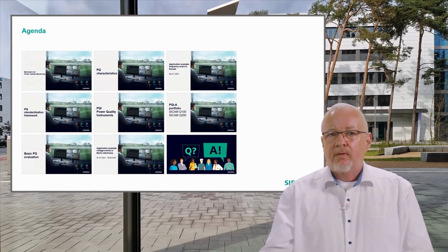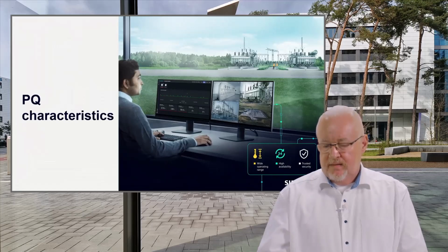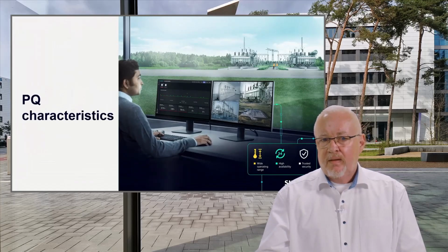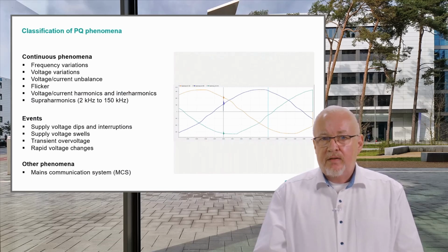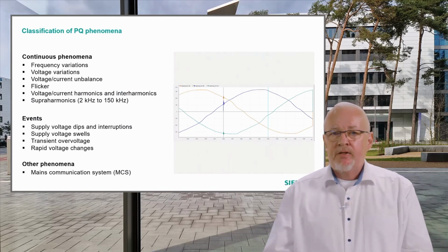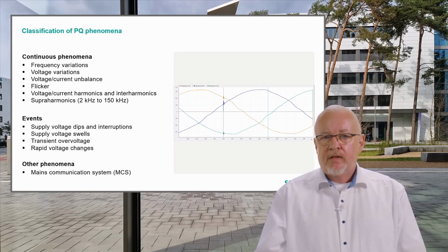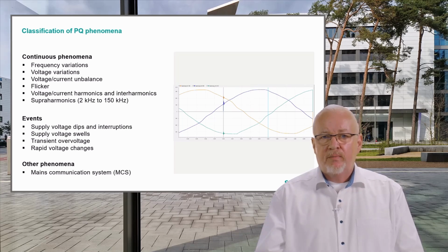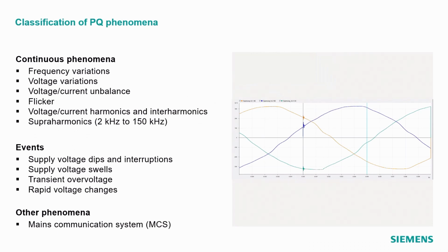Let's have a look at power quality phenomena and events. Type 1 are continuous phenomena like frequency variations, voltage or current unbalance, flicker, voltage or current harmonics and interharmonics, and supraharmonics in the frequency range from 2 kHz to 150 kHz. Type 2 of power quality disturbances are voltage events, such as voltage supply dips and interruptions, supply voltage swells, transient overvoltages, or rapid voltage changes.